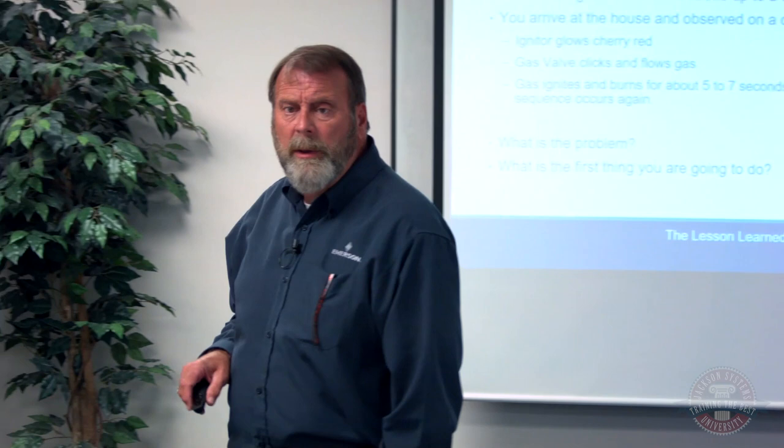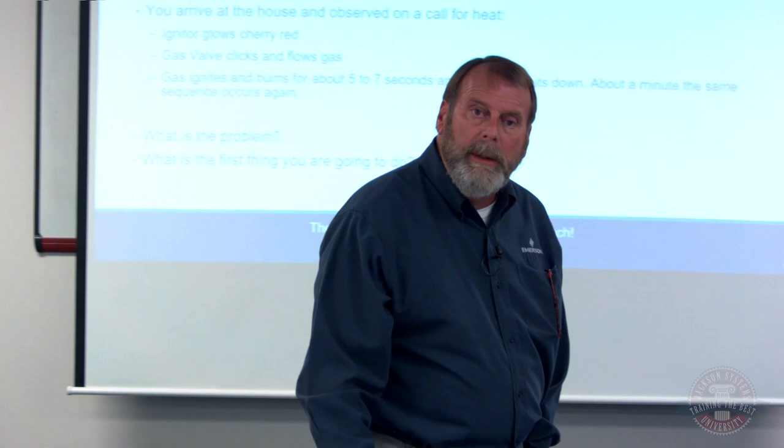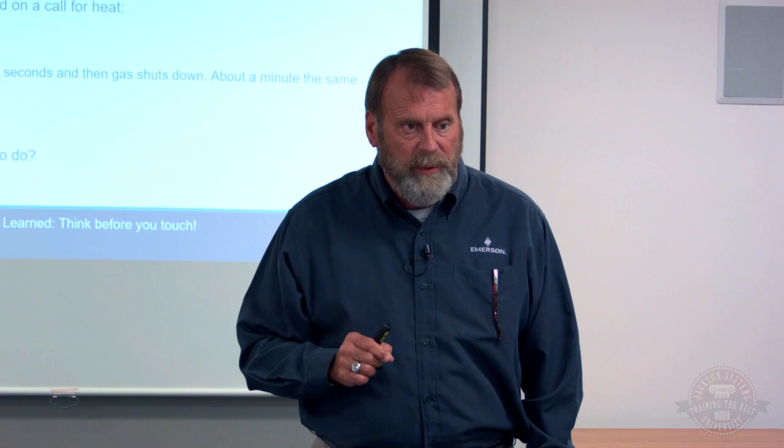What's that? It had to do with the ground. Exactly. The ground. I didn't even think about it. Let's go through and understand how flame rectification works. And don't make the same mistake I did, because here's what's going to occur.